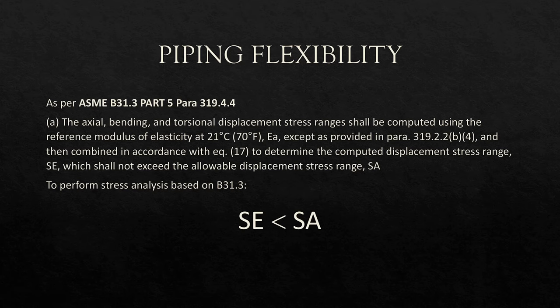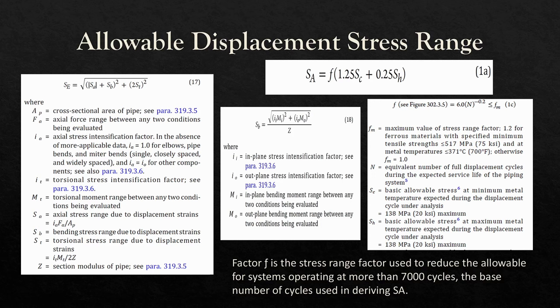As I had mentioned, ASME B31.3 paragraph 319, titled 'Piping Flexibility,' requires us to study the flexibility of the pipe through the thermal action and its effect on the pipe, and requires that stress SE should be less than the allowable stresses. The code also provides these equations to use as limitations for our studies.